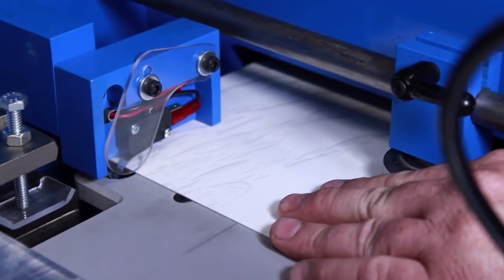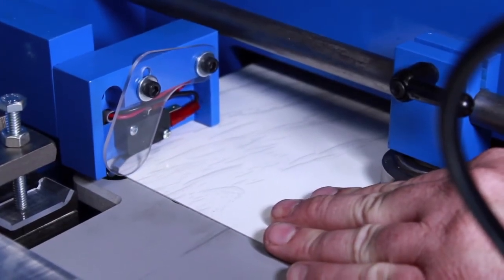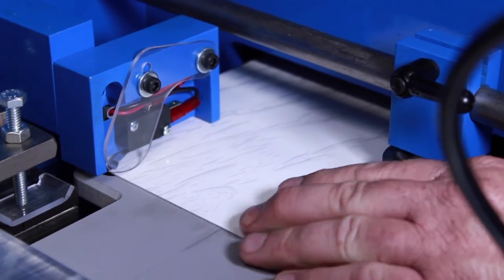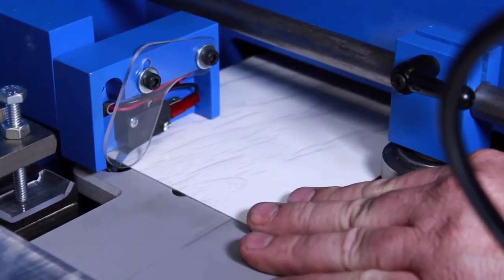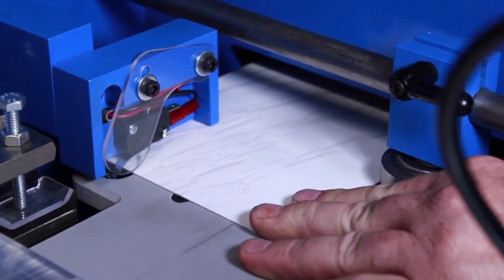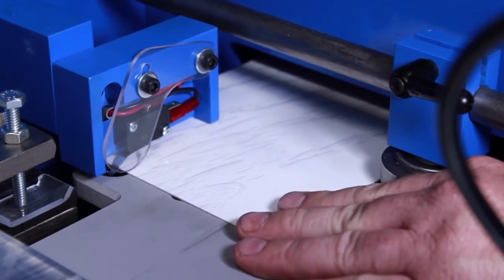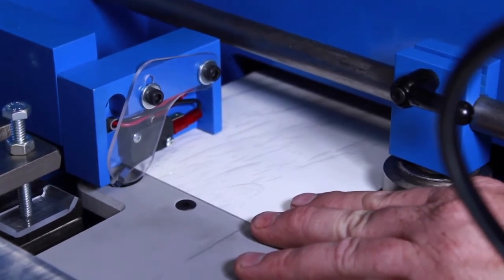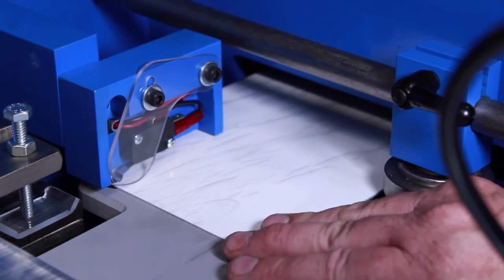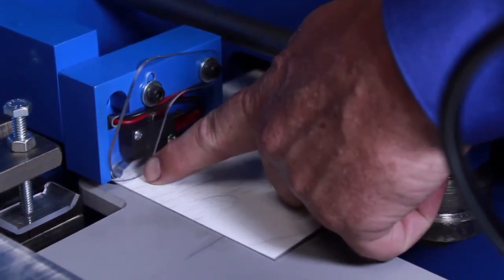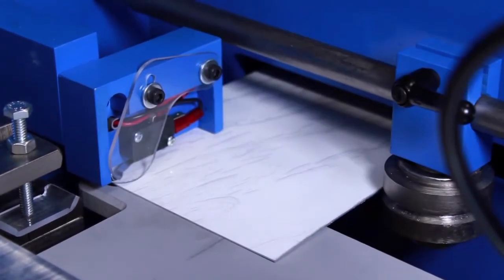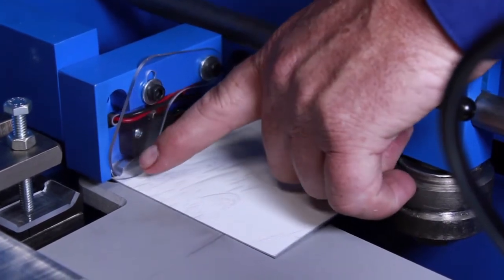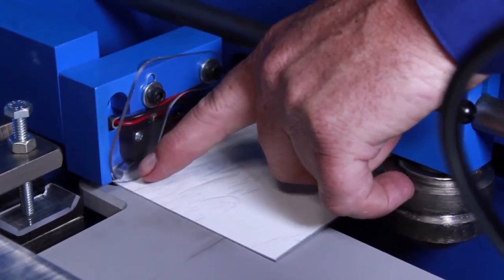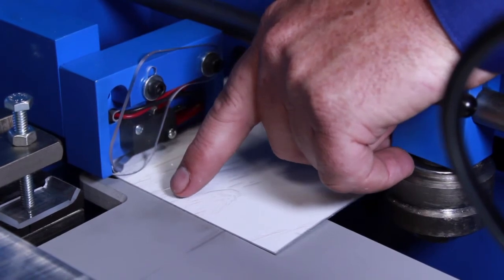To test the limit switch, all you have to do is move the material under it. Now you should hear a click. If you hear the limit switch clicking, then it's adjusted correctly. If there is no clicking, what you want to do is adjust the switch down. Now you can do that in a couple ways. If you're careful, you can grab that metal lever and bend it down slightly.